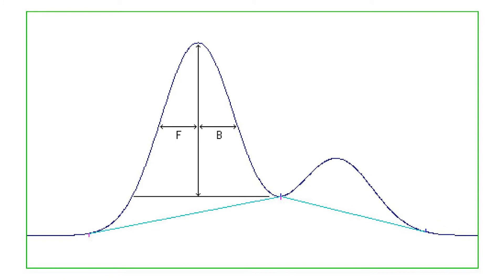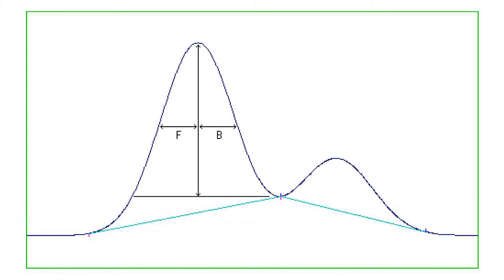Even more than peak width measurements, peak shape measurements become tricky when the peak shares a common baseline with the adjacent peaks. Ideally, chromatographic peaks are purely Gaussian and completely symmetrical in shape; in practice they are neither. The peak skew provides a measure of the asymmetry of the peak and is defined as the ratio of the back width to the front width. Even severely asymmetric peaks are symmetric near the peak top, so skew is measured near the baseline, typically at five percent or ten percent height. Skew equals B divided by F.